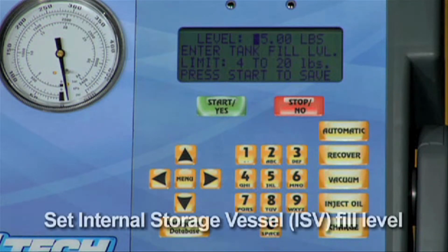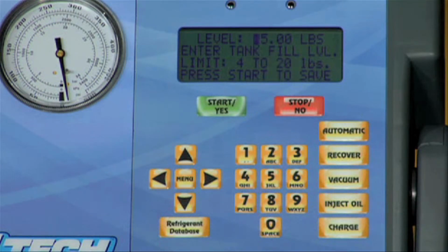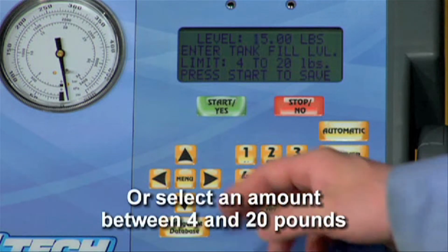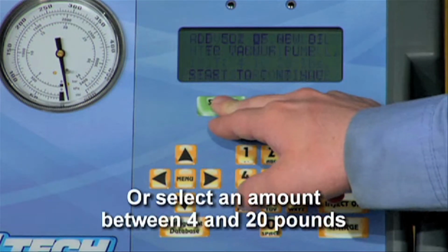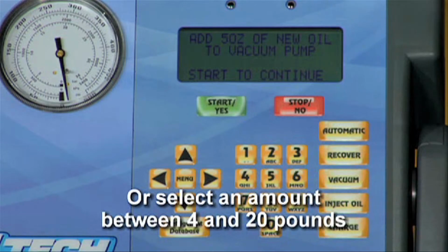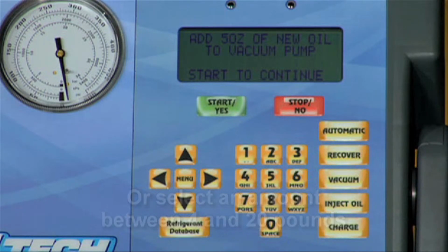The next step is to either accept the unit's preset default weight of 15 pounds or 6.8 kilograms of refrigerant stored in the internal storage vessel, or ISV for short. Or you may wish to change the amount to accommodate your application. Press the Yes key at this time to accept the default amount, or use the keypad to enter a desired amount between 4 and 20 pounds, and then press the Yes key to save the change.